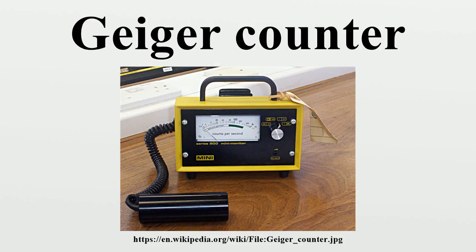However, the GM tube produces a pulse output which is the same magnitude for all detected radiation, so a Geiger counter with an end window tube cannot distinguish between alpha and beta particles. A skilled operator can use distance to differentiate alpha and high-energy beta, but with the detector in close contact with the radiation source the types are indistinguishable.